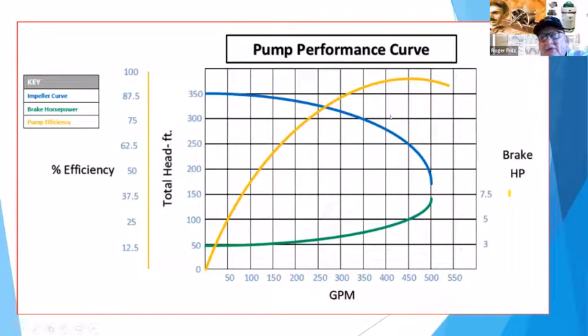So in a closed loop system on a cooling circuit, it's not as critical as it is on an irrigation system, because in an irrigation system you need to stay at the sweet spot of how much head pressure you're going against, and where the sweet spot of the actual horsepower produced is, based on what our actual brake horsepower is. So there's always a sweet spot where the pumps like to operate and run. Well, when you slow this down, the sweet spot moves.